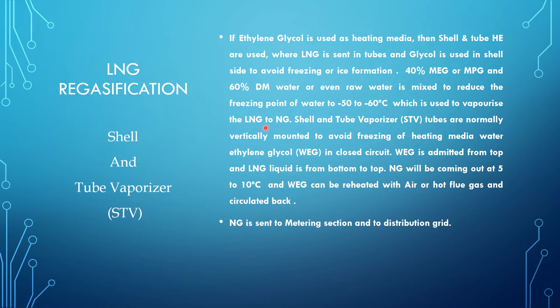WEG is used to vaporize LNG and convert it into natural gas. The STV tubes are normally vertically mounted to avoid freezing of the heating media. WEG is admitted in two ways: the maximum portion flows from top to bottom in counter-current, while a small portion is also sent co-currently to avoid initial ice formation. LNG flows from bottom to top and is converted to natural gas.